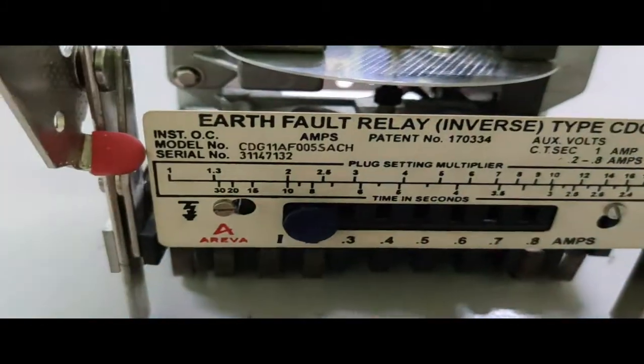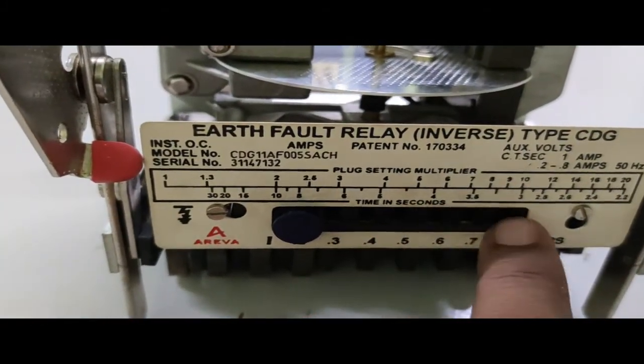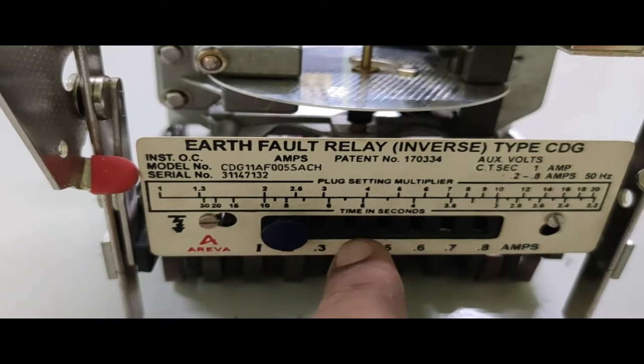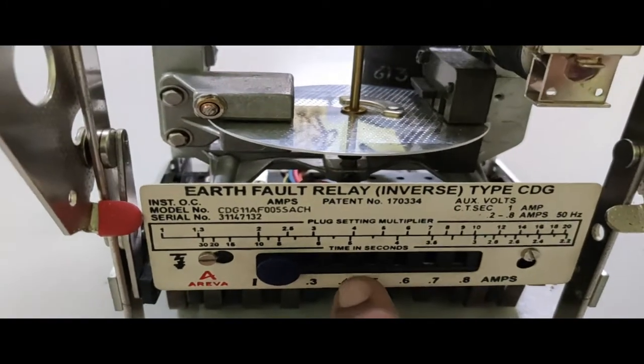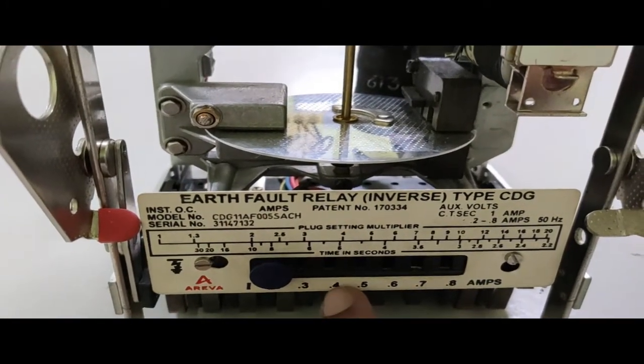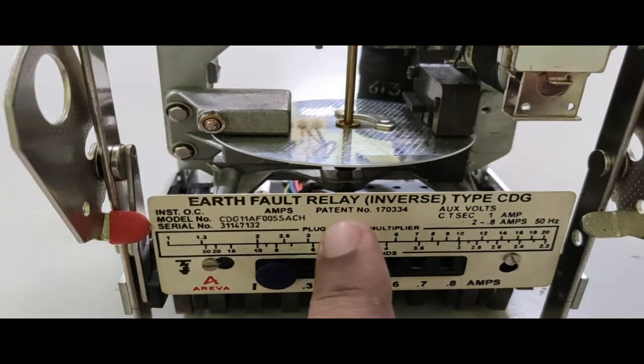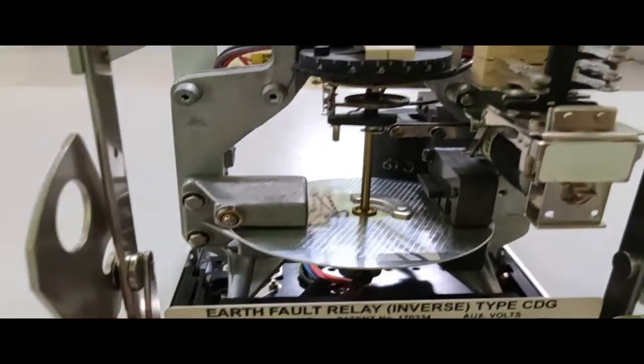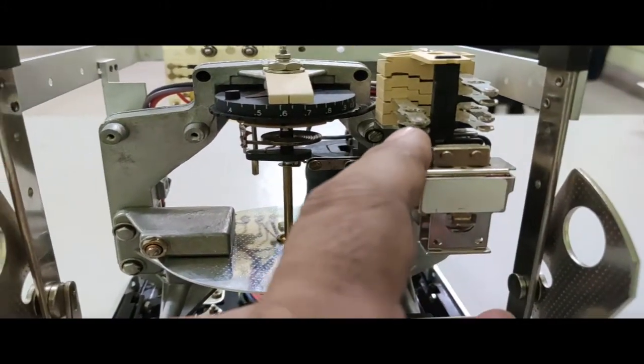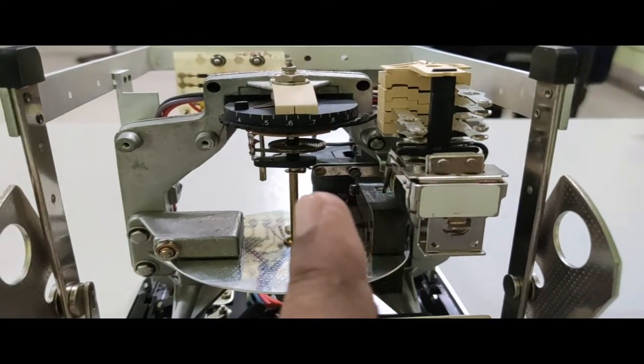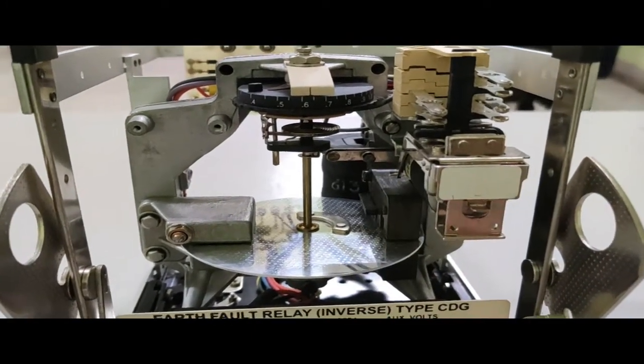Now here, as I mentioned, this is called plug setting. Plug setting means this is the preset value of the current. If the current passing through the relay coil is more than that, then the relay will trip and generate the trip signal. Generating the trip signal means it will short circuit those terminals, and once the trip signal is generated, that signal will activate the circuit breaker.